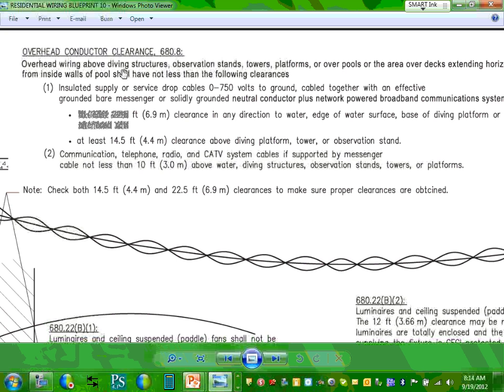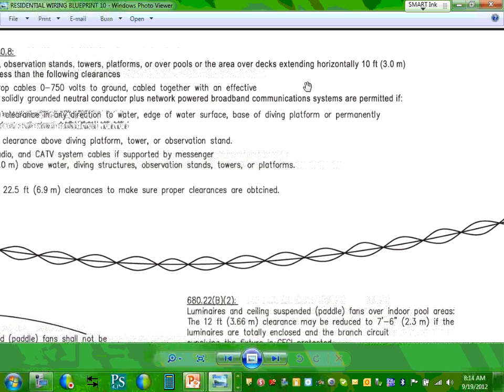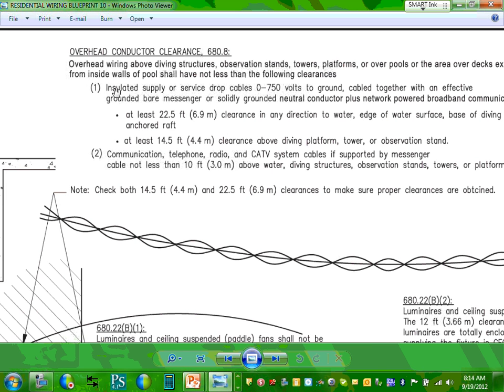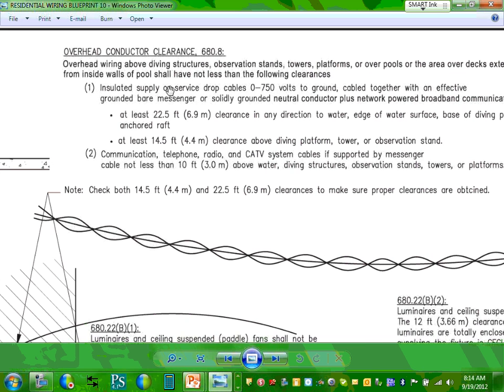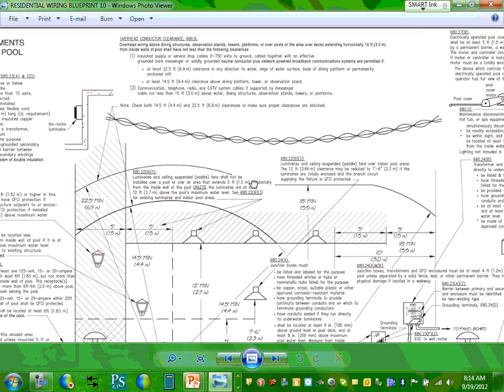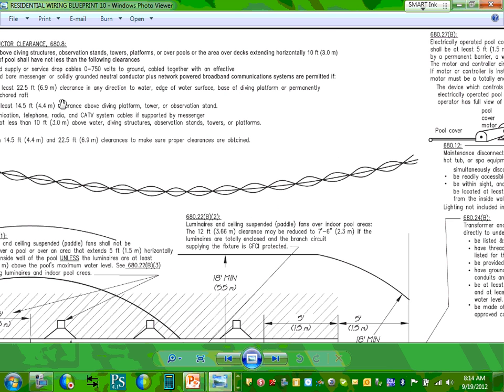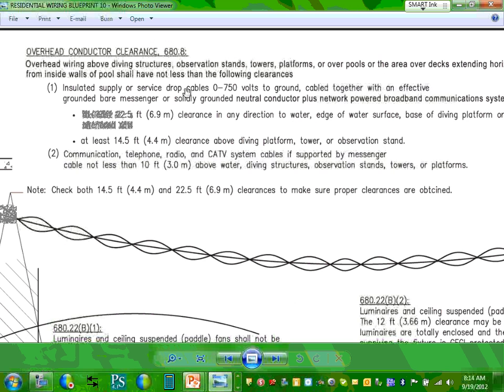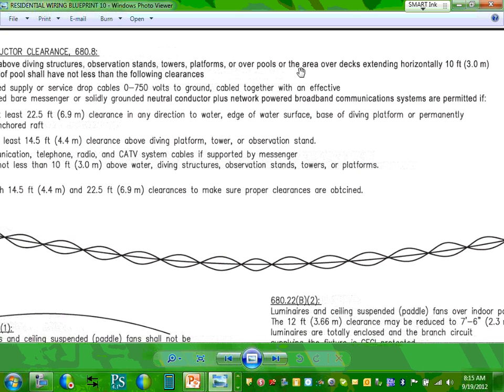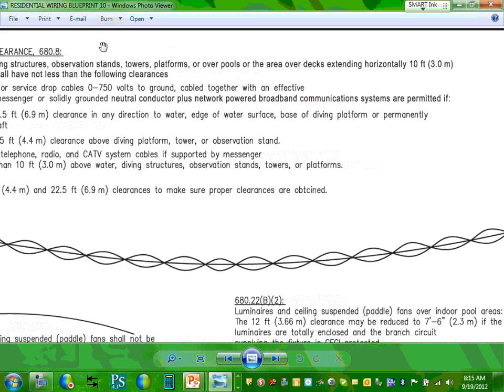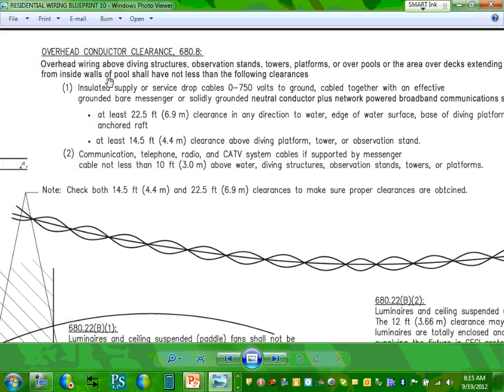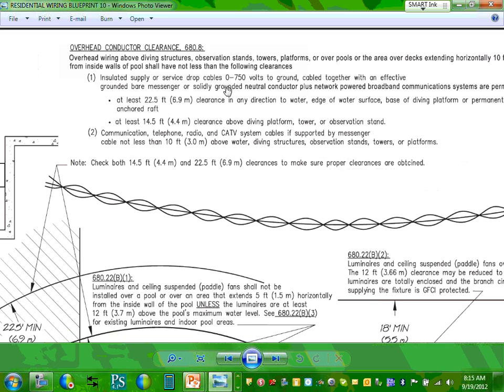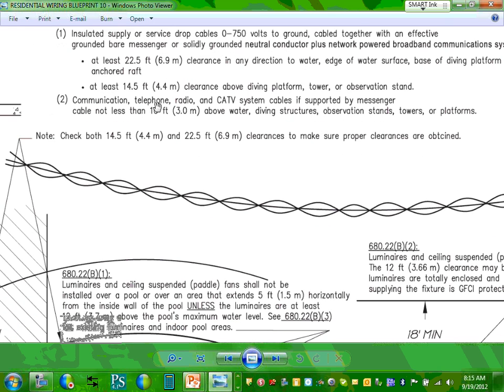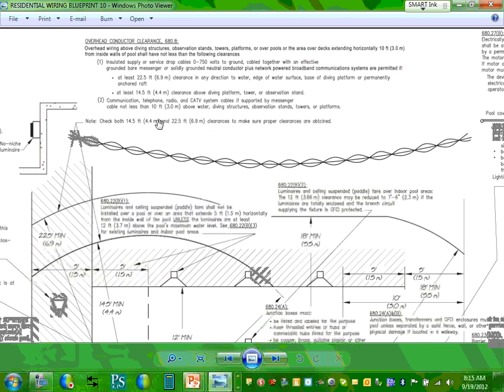So overhead, above diving towers, platforms, areas, decks exceeding 10 feet from inside walls of the pool shall have not less than, so you can't put them right above the swimming pool, and you have to maintain clearances. Look at the clearances you have to maintain. 10 feet away from the swimming pool, and you have to maintain all these clearances for them. So overhead wiring above diving, all these areas, platform, extending horizontally 10 feet from the inside wall of the pool shall have not less than the following clearances. So you have all these clearances, 22, 14, and 10. Any comments, guys, about these? The rule, guys, is you don't bring power lines right above the swimming pool.